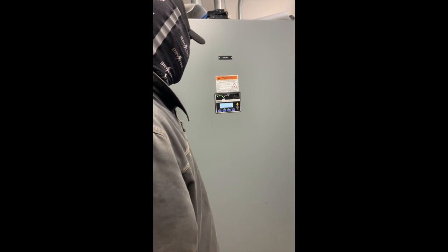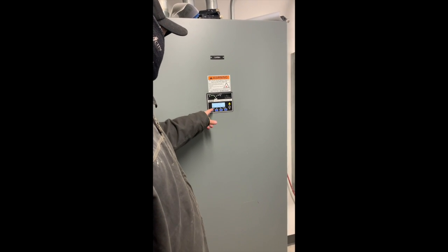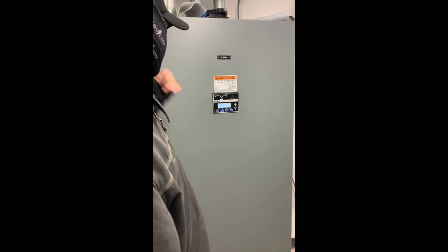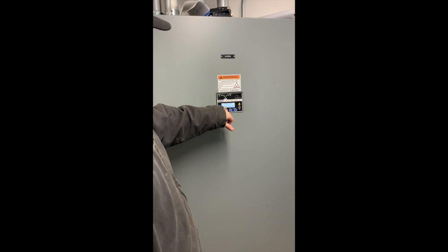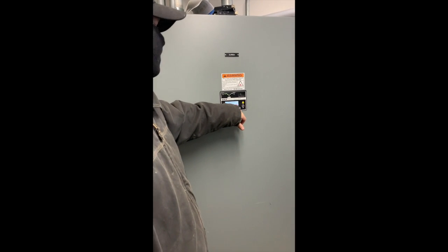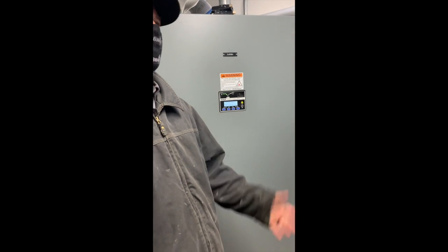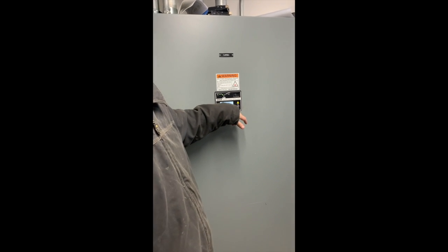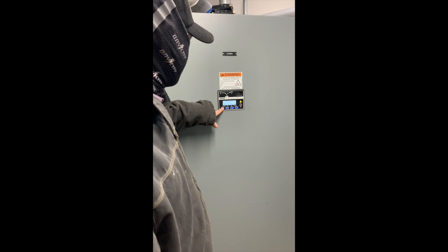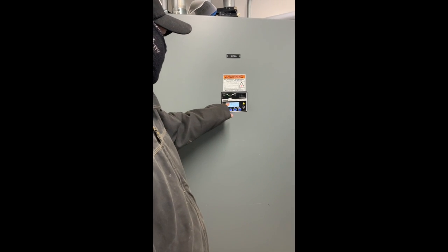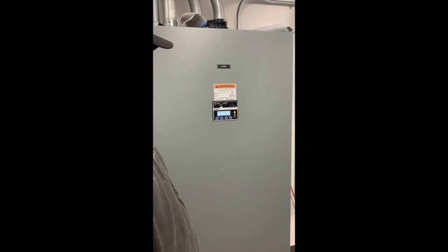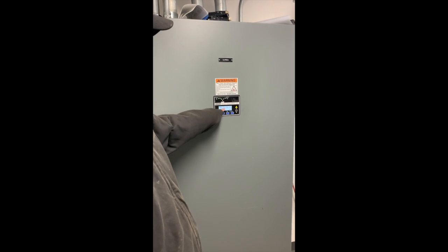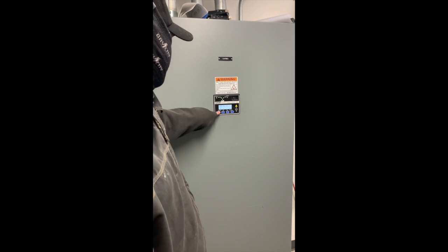Down here, you can see the normal source voltage that you're getting from PG&E. The emergency is at 0 because the generator's not running. As soon as the generator is running, you'll see the red light here, and then you'll see the voltage output from the generator. You can click down. Down right here will give you all the different leg to leg voltages on the normal source at 60 hertz. Hit down one more, that's your ground to leg, or leg to ground. And then you hit down.